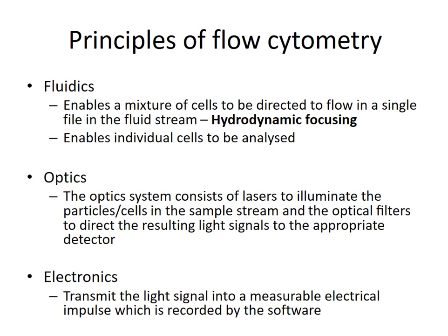And of course, this process of hydrodynamic focusing enables cells to flow in a single file and as a result be analysed individually. The optics consist of lasers to illuminate the particles or cells, or the fluorochromes as we'll come across, and the optical filters will enable different lights of different wavelengths to be directed to certain detectors. So that's the job of the optics, to separate the light that's being deflected by the cell according to wavelength towards a specific detector which will enable us to detect certain markers of a cell.